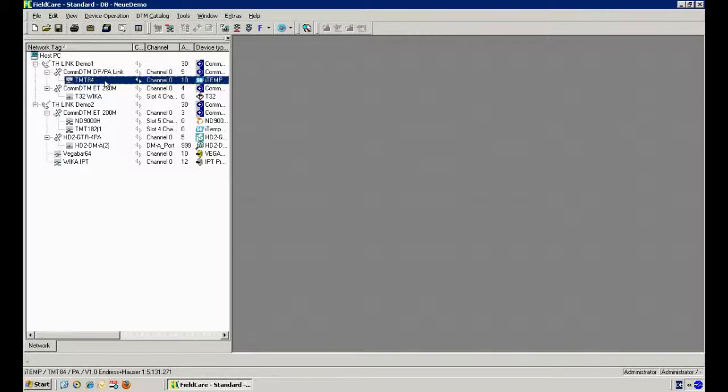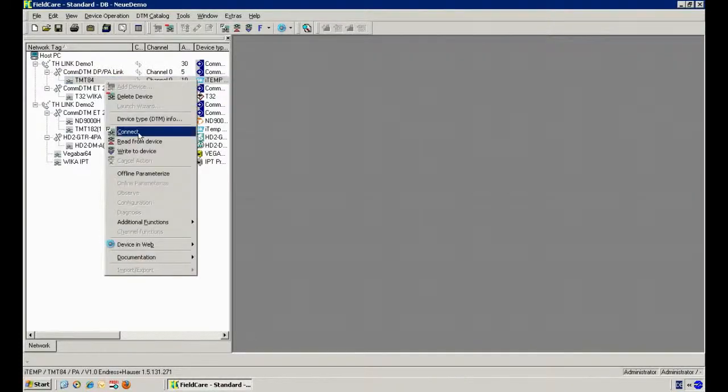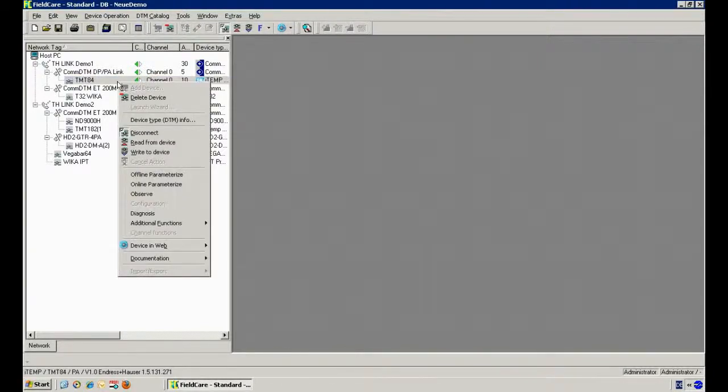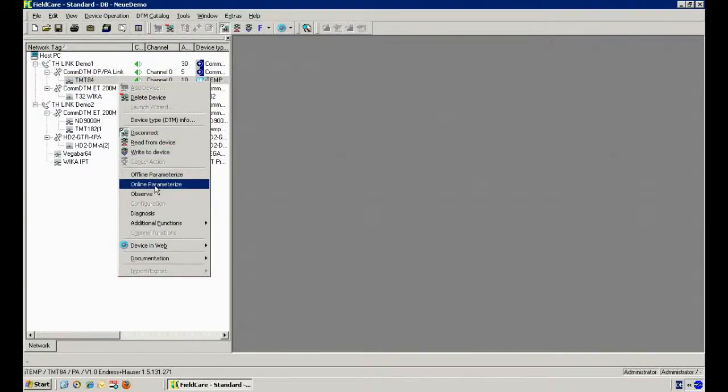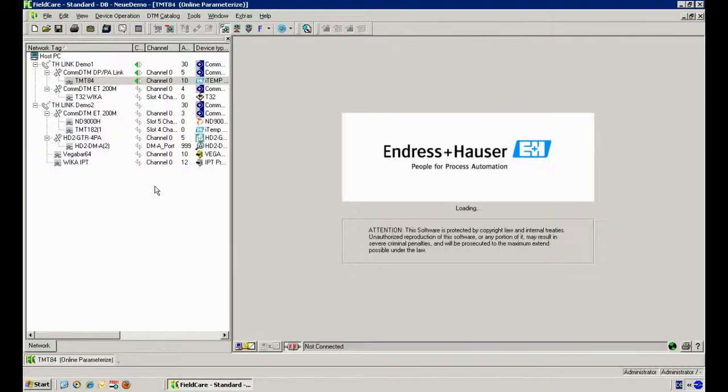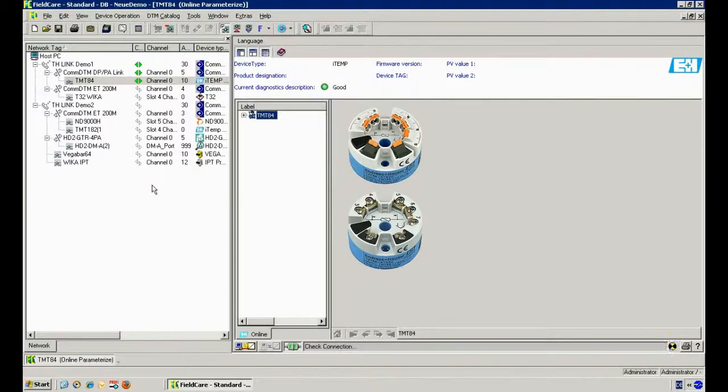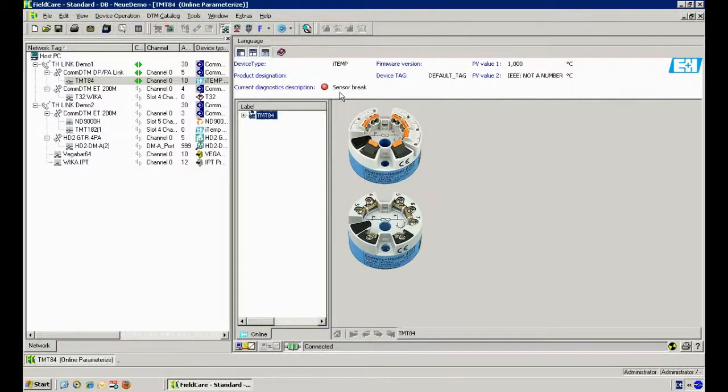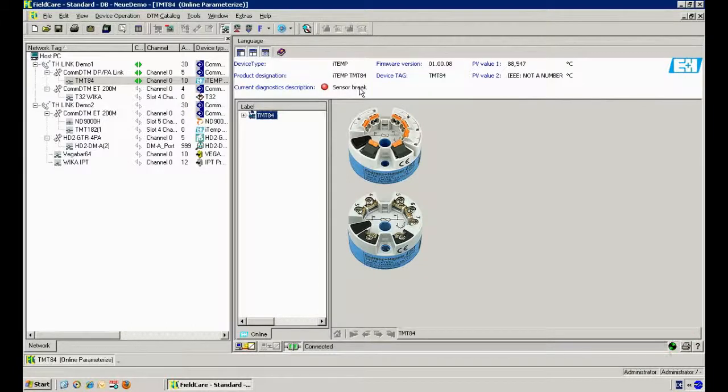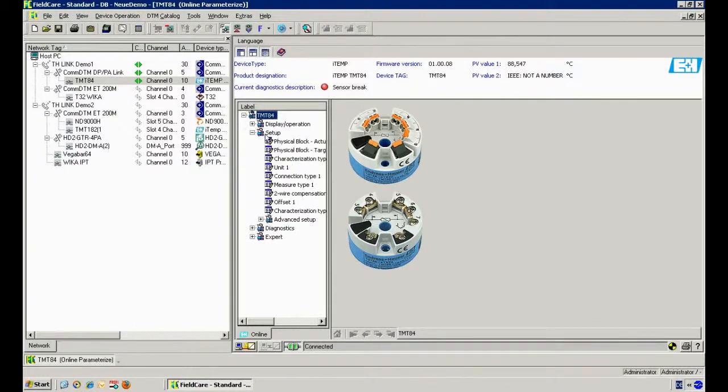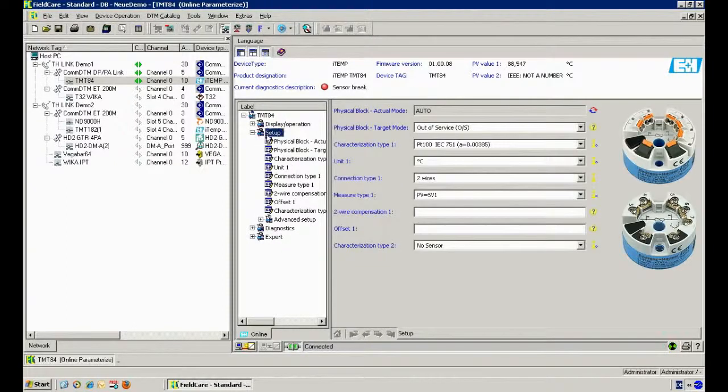Using the context menu I can go online now to the device and open the online parameterization to use the DTM from this device. What you can see here very clearly is diagnostic information: sensor break. That means we have exact information what the problem is and the device DTM provides a lot of functionality.